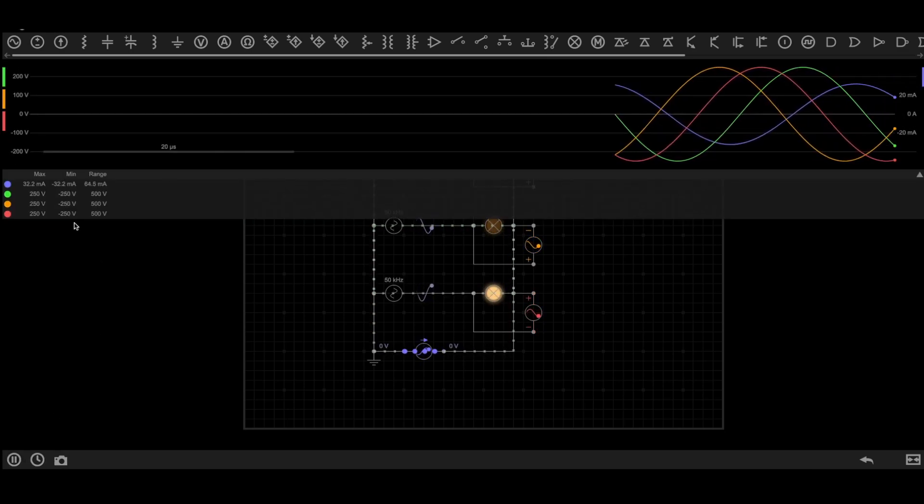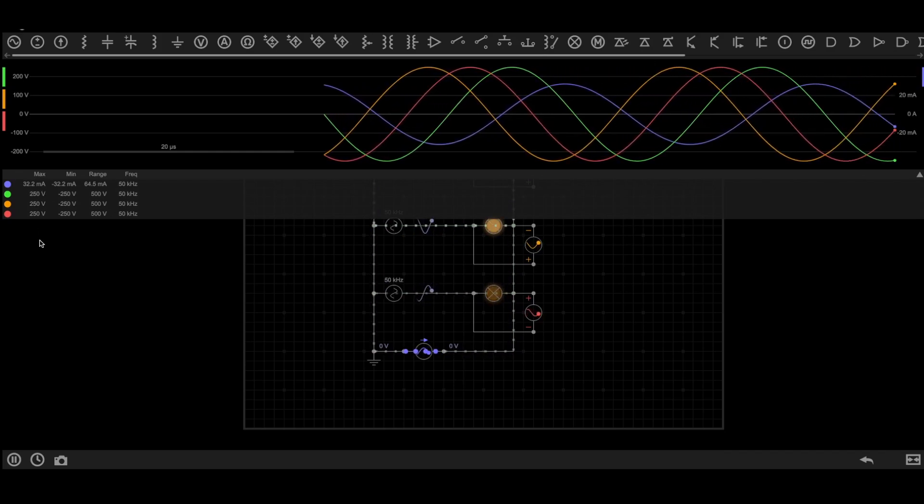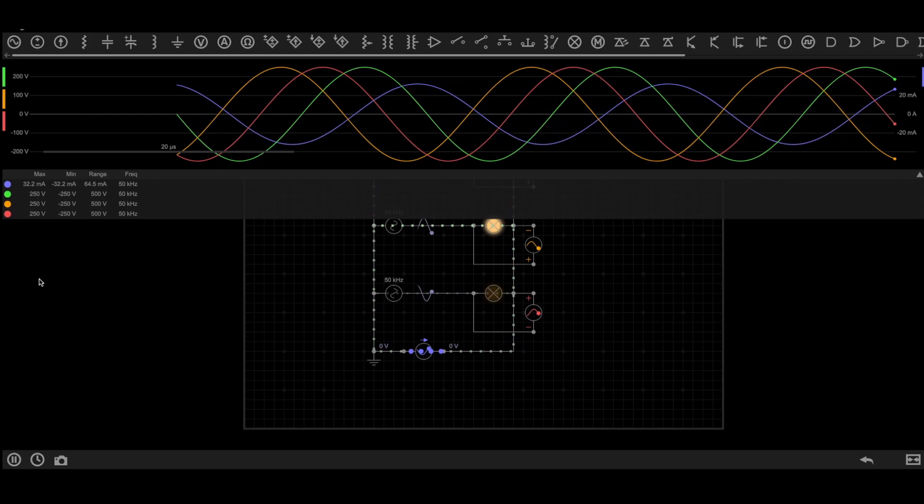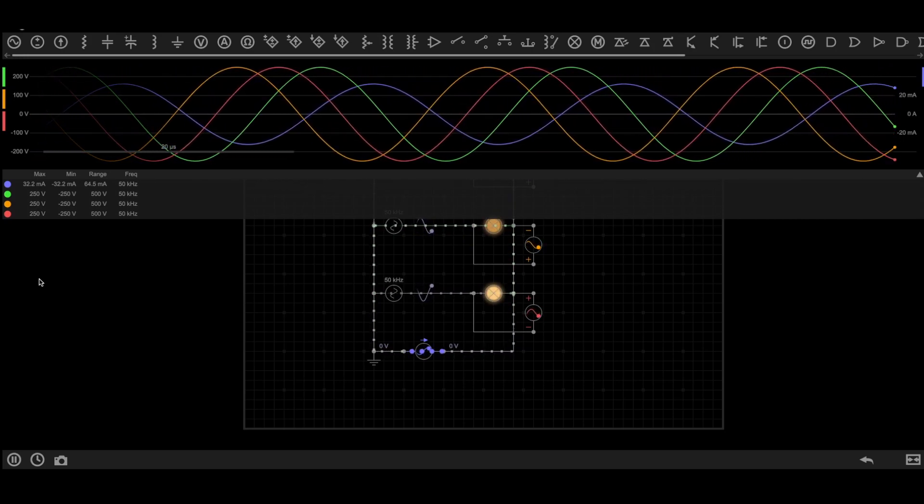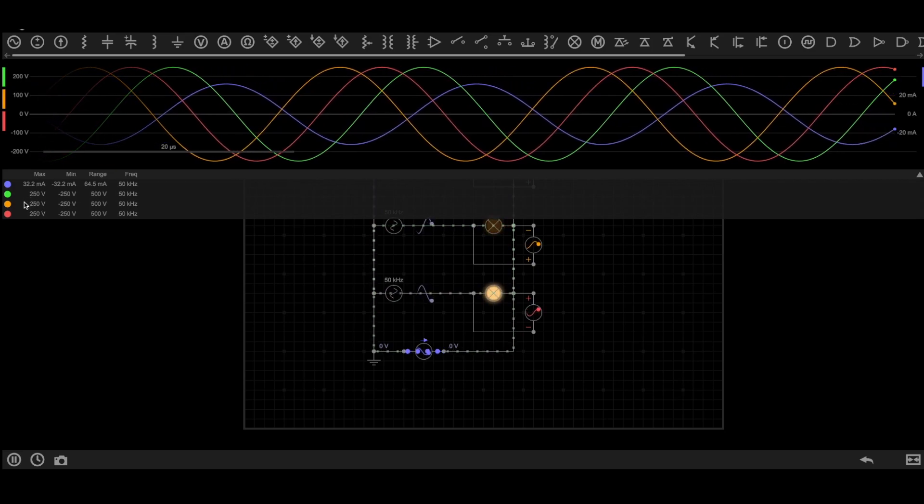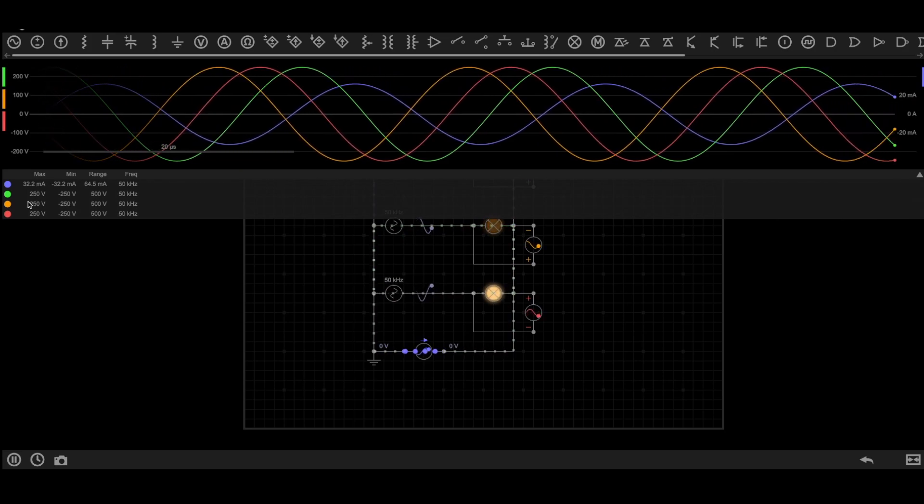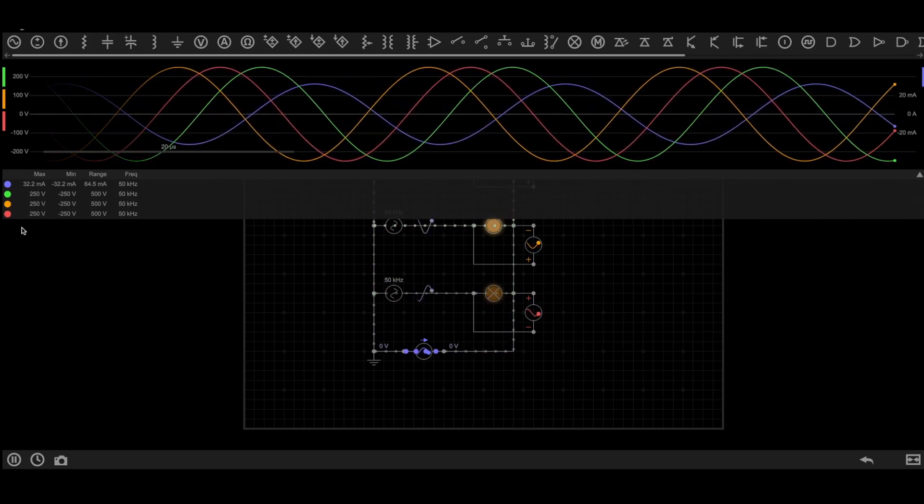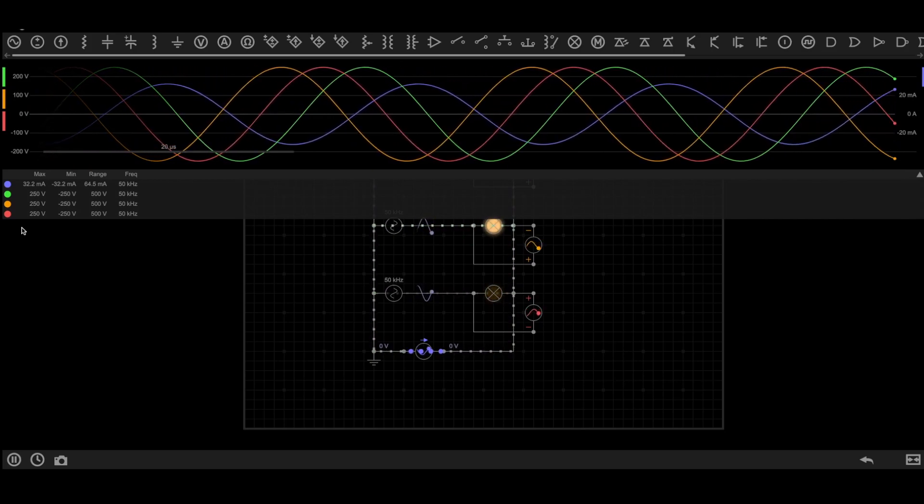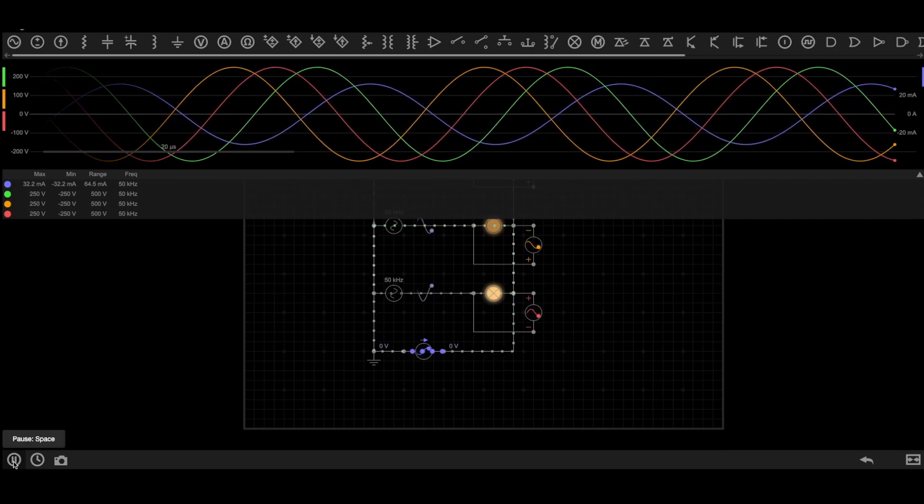As you can see, the ammeter is now reading 32.2 milliamperes. This is the current coming because of the unbalanced load, which proves our second statement. Now even if the load is unbalanced, you can see voltage across each load is constant at 250 volts. Here are the readings of voltmeter. That's the reason why you need neutral in distribution systems. This is why neutral is so important in distribution systems.